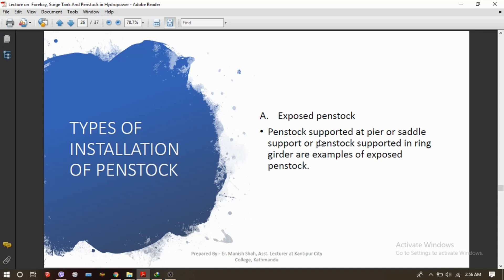Now, what are the types of penstock installation? The first type is exposed penstock. An exposed penstock is one that is supported on a pier or saddle support, or supported in a ring girder — meaning the whole penstock can be seen from outside. Generally, penstocks are supported by pier or saddle at every five meter interval.